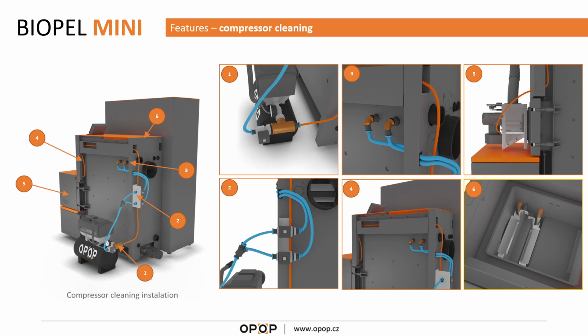Accessories, compressor cleaning. Here you see the assembly for the compressor cleaning in detail. In the manual there is step-by-step process how to connect the accessories, so you can just follow the manual, and you can connect all these fittings with no problem. So here in the left picture you see the compressor, and basically there are two hoses. Blue one is for the heat exchanger, and the orange one is for the burner cleaning. The orange hose goes like this to the top, and then behind the covers goes to the front, and it's connected to the burner here.